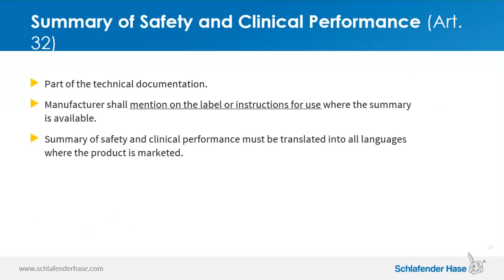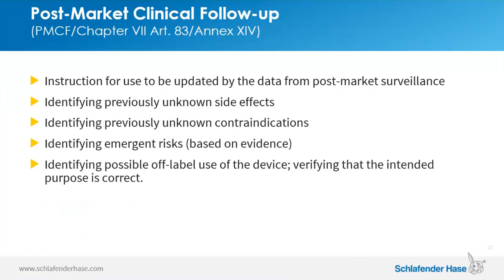The post-market clinical follow-up is another important topic emphasized by the MDR. MDR in general pays a lot of attention to post-market surveillance. This means that the manufacturer is obliged to observe the product as it goes through its life cycle while being on the market in order to monitor any side effects, emerging risks, and off-label use.